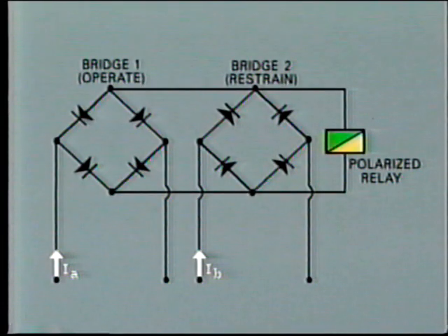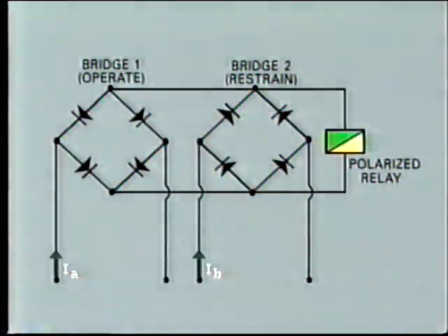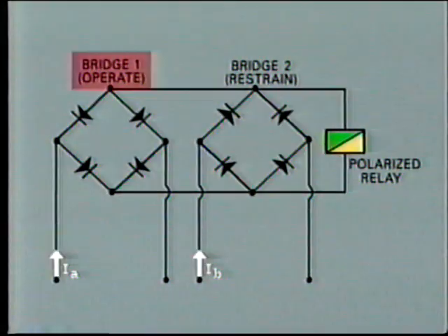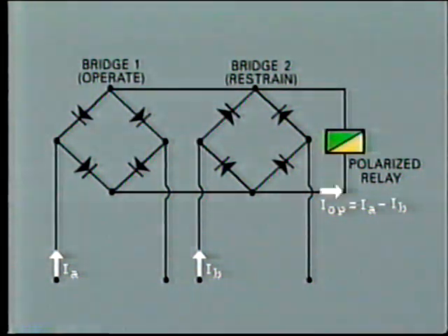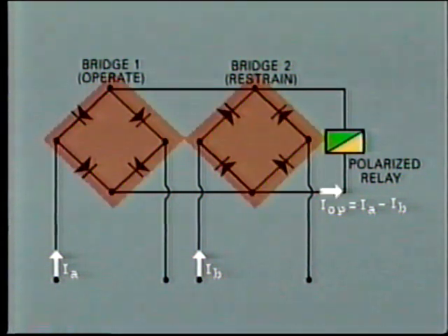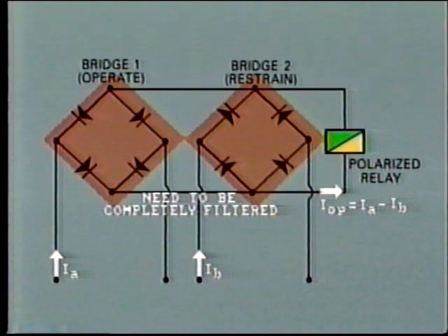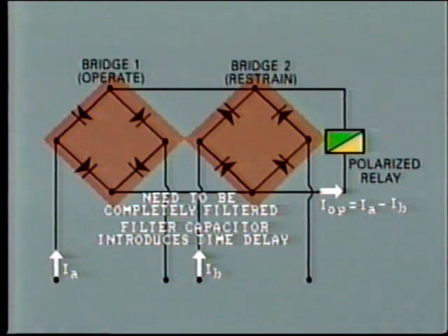In one common type of amplitude comparator, the two incoming signals are rectified and connected in opposition. That is, one to trip and one to restrain. The resultant DC signal represents the difference, IA minus IB in this instance. To provide direct comparison, the rectified signals need to be completely filtered. A disadvantage of this is that a filter capacitor introduces a time delay.